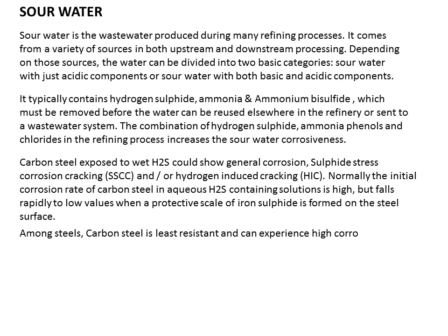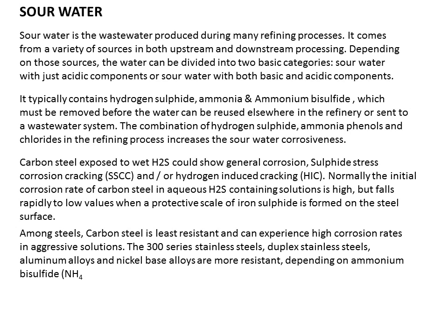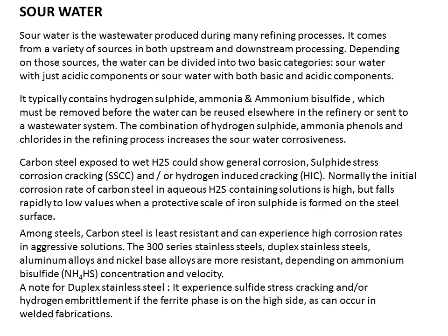Among steels, carbon steel is least resistant and can experience high corrosion rates in aggressive solution. The 300-series stainless steel, Duplex Stainless Steel, Aluminium Alloys, and Nickel-base Alloys are more resistant, depending on Ammonium Bisulphide concentration and velocity. Caution: Duplex Stainless Steel experiences sulphide stress cracking and hydrogen embrittlement if the ferrite phase is on the high side, which can occur in welded fabrications.